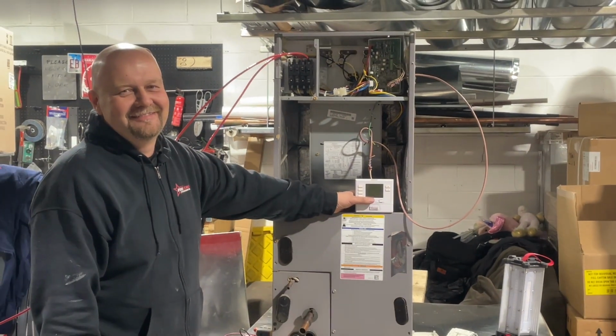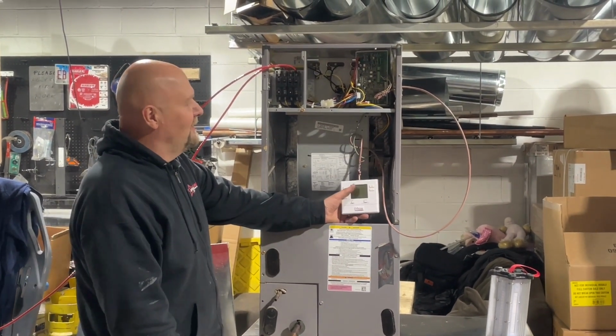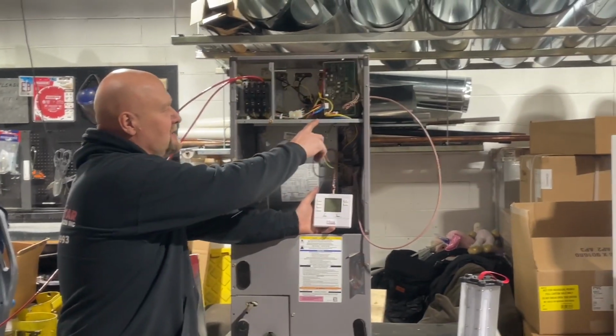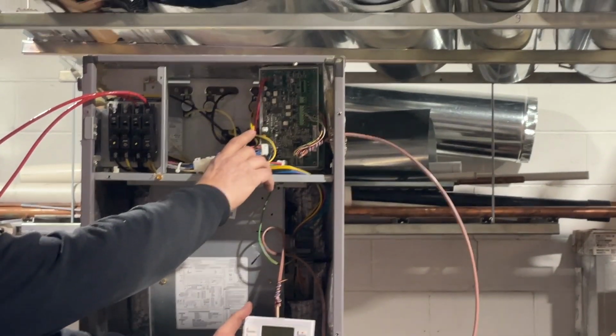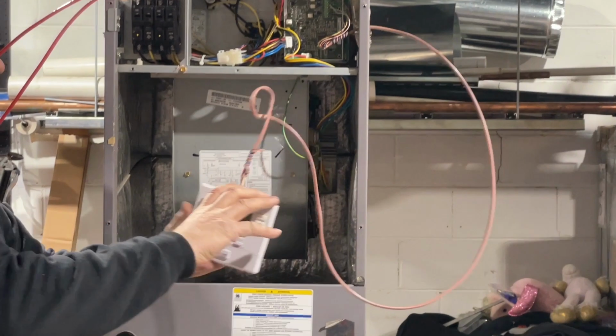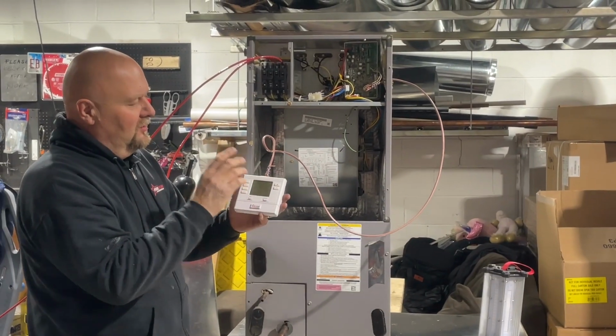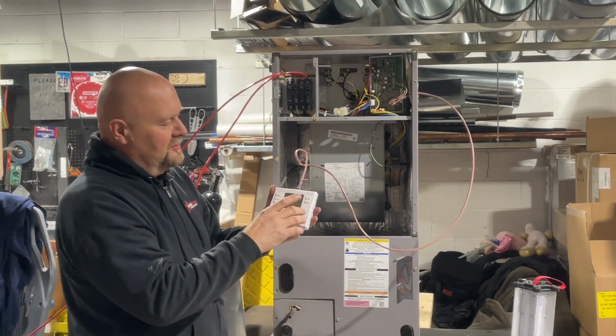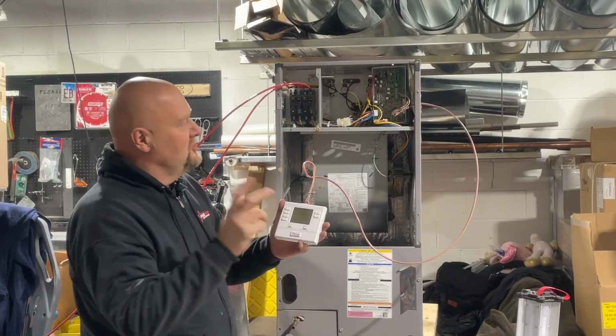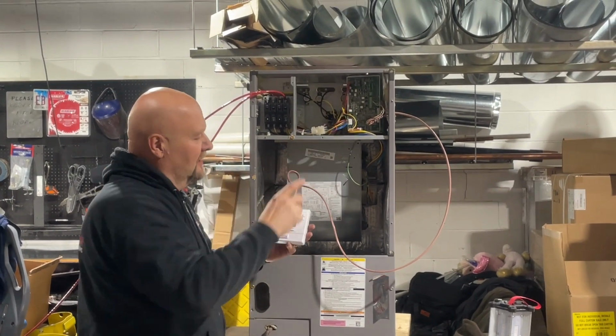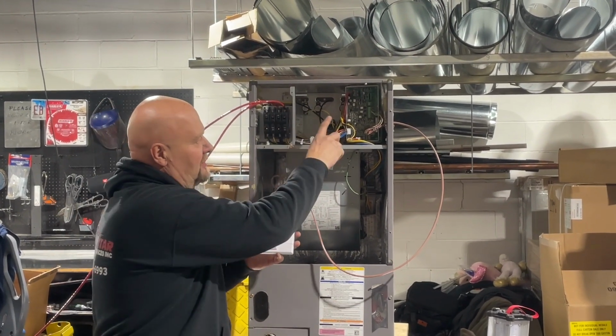Okay, sequence of operations. So 24 volts from the transformer goes to the control board. The control board will send 24 volts to the R terminal on the thermostat. When there's a call for heat, the thermostat will send power to both the G, or the call for a fan, and W to turn on the electric heat.